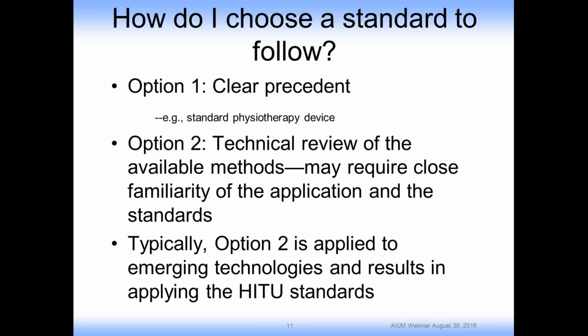So a common question is, how do I choose to follow a particular standard? Well, in the first case, if you have a fairly standard device that has clear precedence, then that makes it simple. For example, as I mentioned, physiotherapy has been in use for many decades. If you have, for example, an unfocused device in the range of 0.5 megahertz to 3 megahertz, as mentioned in the scopes of the standards, there is a clear justification for following that, and if it's lower than the output limits, 3 watts per centimeter squared, there's a clear justification for following that, given that it's so similar to many other devices.